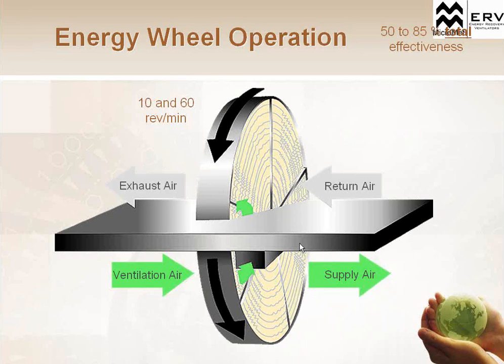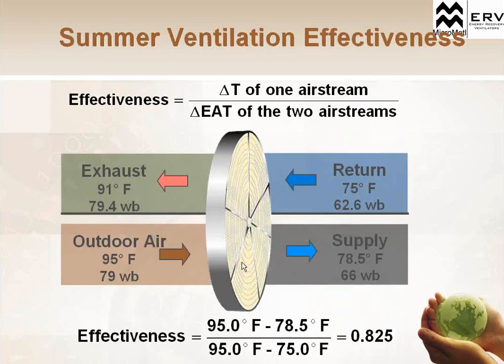Now, these energy recovery wheels are going to spin at a very low RPM, between 10 and 60 revolutions per minute. So that's a really slow revolution rate. We're not using a lot of energy to move that wheel. We're using one simple belt to rotate the wheel, so there's not a lot of mechanical pieces that can go wrong with this system. And it does a really great job of transferring that energy. We'll talk a little bit more about the wheel itself, but that's basically how they work.